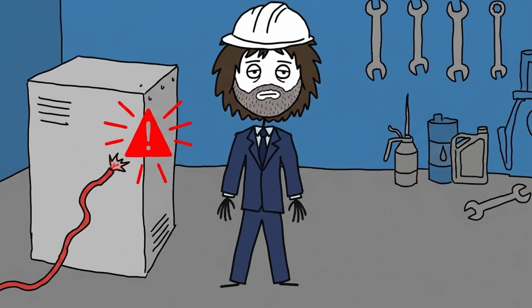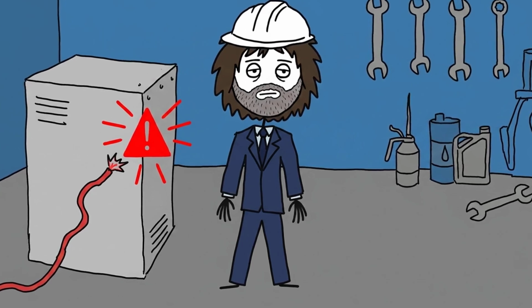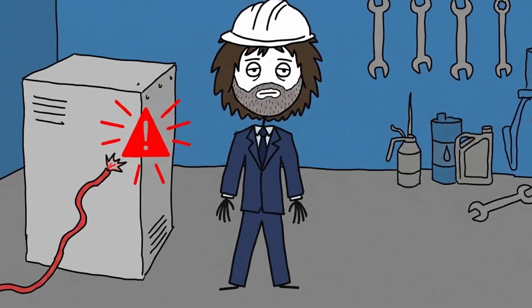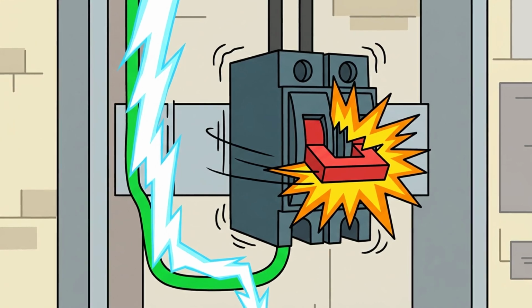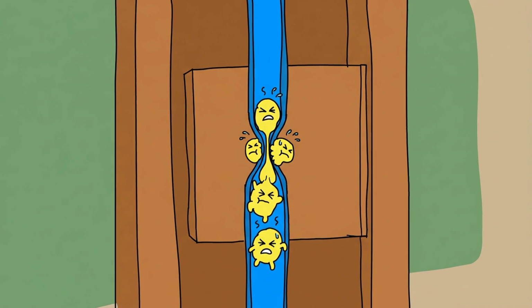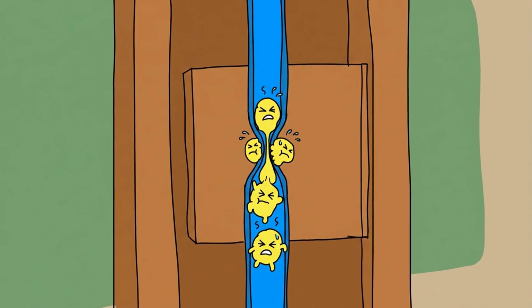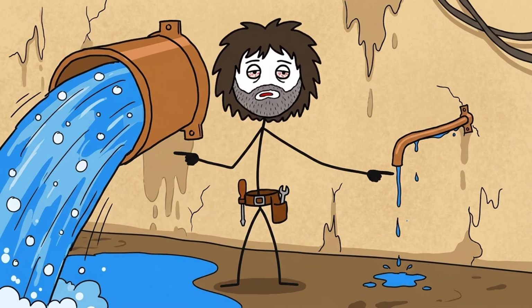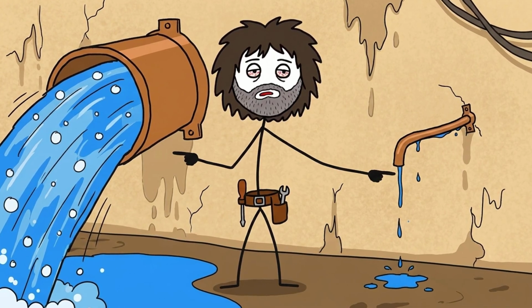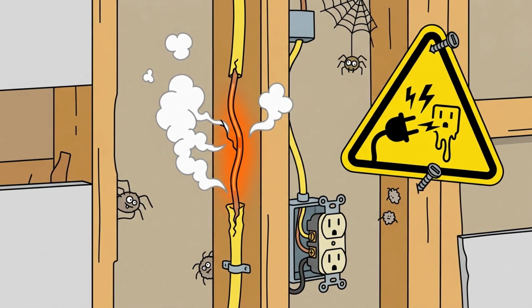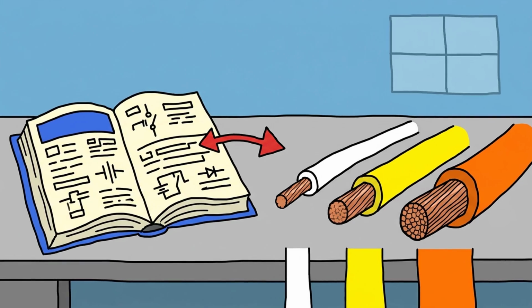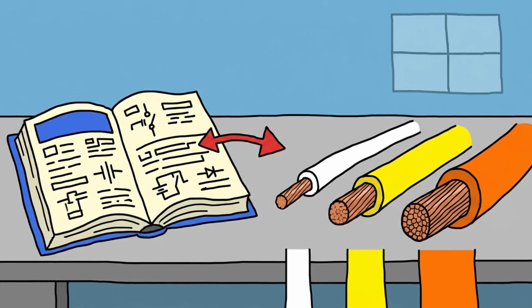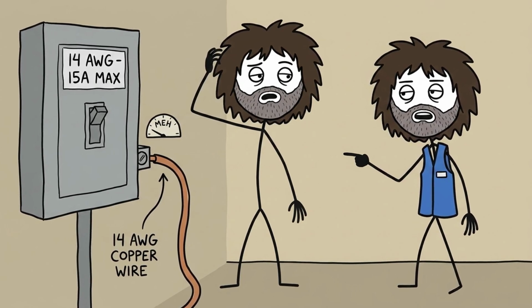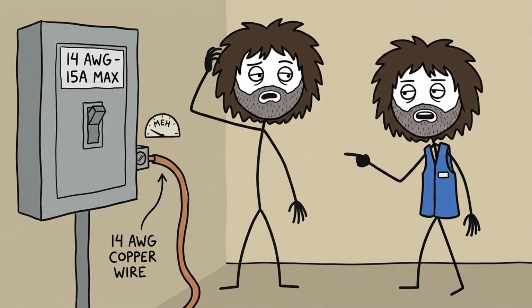An AFCI breaker contains an onboard microprocessor that constantly analyzes current waveform signatures. It filters out benign motor sparking and looks specifically for irregular, high-frequency radio noise characteristic of hazardous arcing. The moment the microprocessor recognizes an arc fault signature, it fires a solid-state trip signal, cutting off power before surrounding wooden studs catch fire.